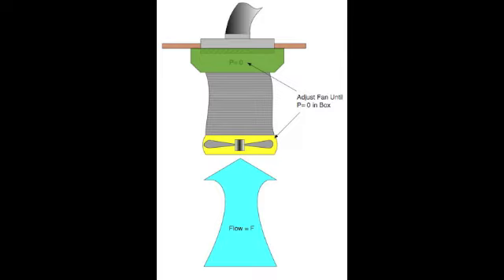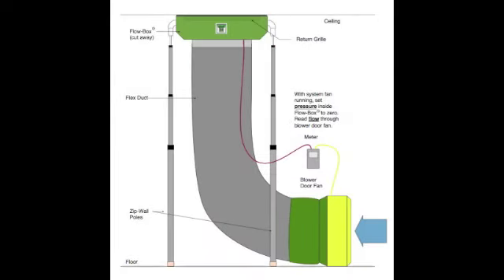Also, the fact that the pressure in the box is the same as the pressure inside the room means that the air flow into the return grill has not been affected by the box. A good powered flow hood should have a way to hold the box firmly in place and use a calibrated fan flow meter device, for example, a good quality calibrated blower door fan with a manometer. The manometer should read the pressure inside the box and display the fan flow simultaneously.